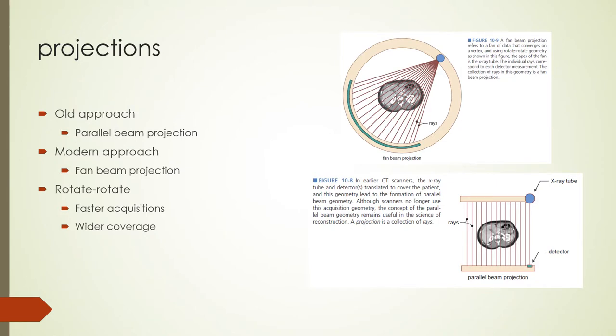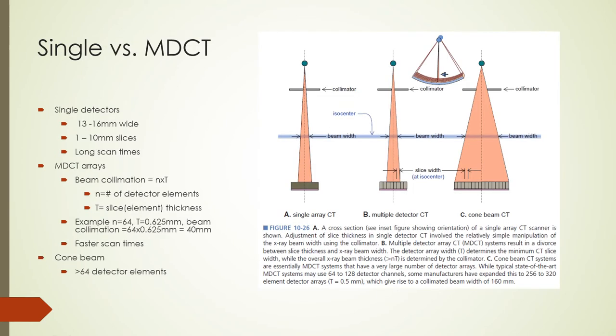Fan beam projections are a common projection mode compared to parallel beam projections. Each ray forms a projection of data at the location of each detector element. With rotate-rotate geometry, scans can be acquired quickly. In early CT scanners with single detector channels, the displayed slice thickness was determined by the X-ray beam width through collimator adjustments; detectors were 13 to 16 mm wide and by collimating, 1 to 10 mm slices could be achieved. Single array detectors had long scan times making breath-hold scans impractical.